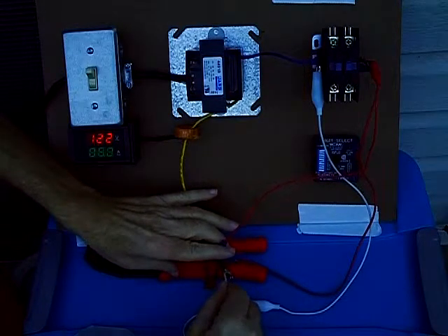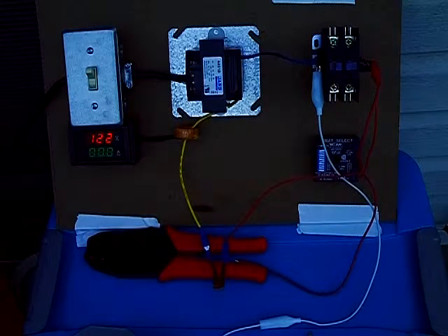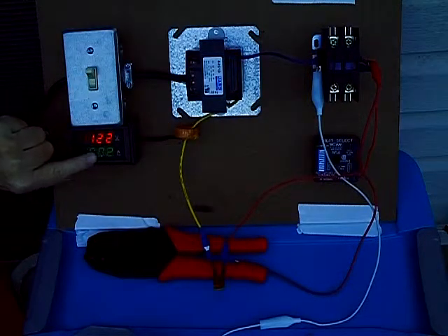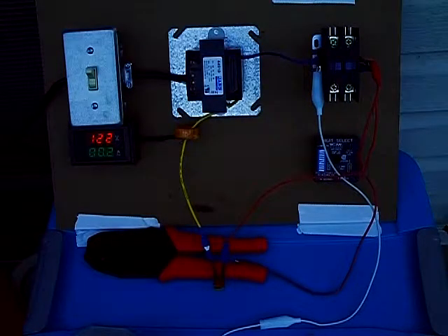I'm going to create a short, and I took or eliminated the short, and it's going to allow this to time out and reset again. The purpose of this is to save the service technician a go back with a very upset customer, because a lot of service techs will guess at where the short is, and they'll replace the wiring going outside. They'll change out circuit boards, thermostats, and it could be an expensive repair. And if you didn't find the short, you hear the contactor kick back in. We got 0.2 amps right here on our current draw. Everything's working fine. The reason I do this is because if you didn't find the short and you did an expensive repair, that customer is going to be very upset at you and your company.